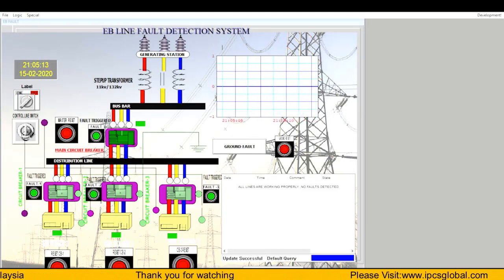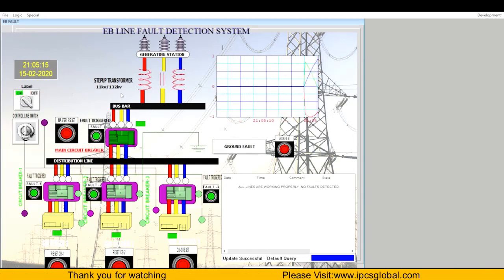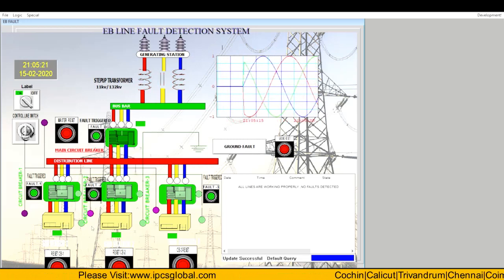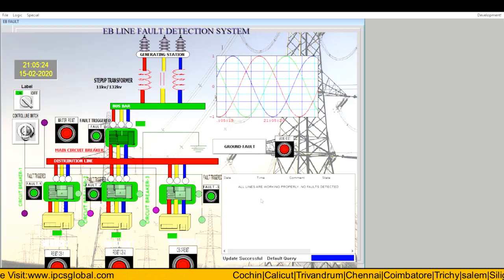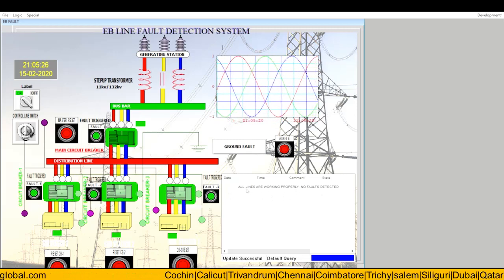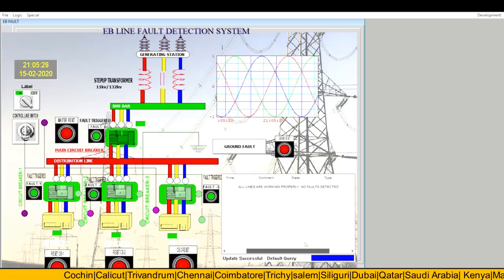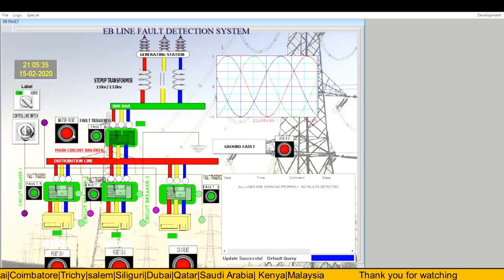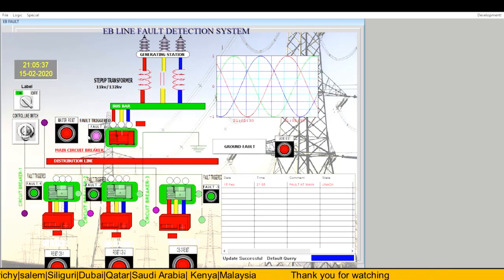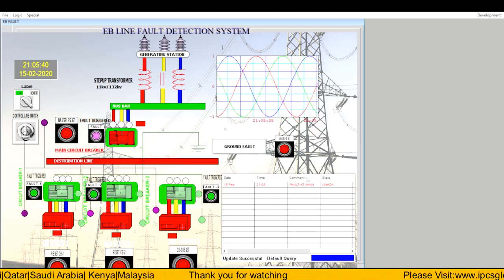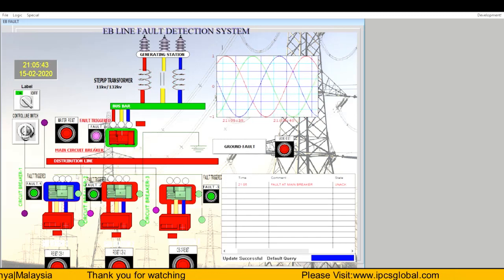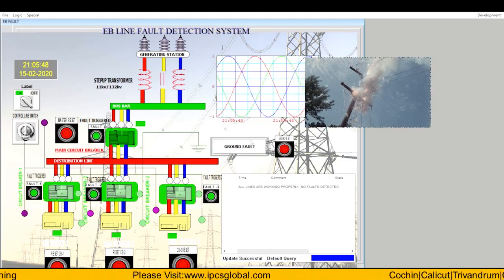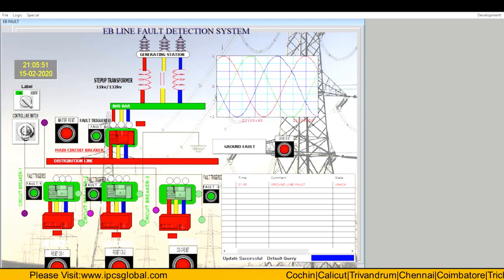This SCADA software is called the EB Line Fault Detection System. This SCADA software monitors the flow of electricity through transmission lines and substations. When the operation is turned on, the step-up transformer steps up the voltage and the current passes through the distribution lines and reaches the other substations. The software contains an alarm system — when a fault is detected in the line, an alarm is raised. Whenever there is a fault in the main circuit breaker, it can be due to birds sitting on the transmission lines or objects hitting the transmission lines. When this fault takes place, the current supplied to other substations stops.